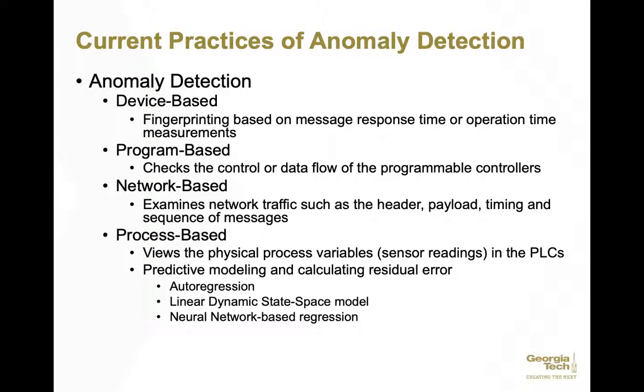And then the last one is process-based, and it views the physical process variables, sensor readings in the PLCs, and then calculates, based on predictive modeling, the residual error. It uses things such as autoregression, linear regression, linear dynamic state space models, neural network-based regression, LSTMs, which are long short-term memory networks. Basically, those models are just predicting ahead of time, and then there's an error component, which is what's actually happening, and that's called residual error.